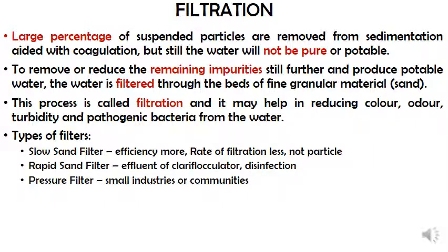Filtration. A large percentage of suspended particles are removed by sedimentation aided with coagulation as well as by plain sedimentation, but still the water will not be pure or potable. To remove or reduce the remaining impurities still further and produce potable water, the water is filtered through beds of fine granular material, usually sand.